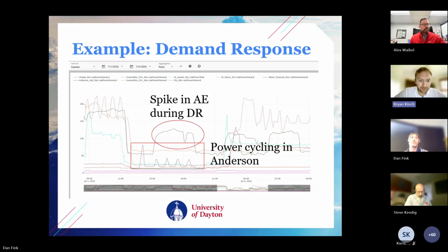So this example is during the demand response event. AE is Albert Emanuel, that's our admissions building. Somebody in Albert Emanuel called an HVAC tech and said, hey, turn our HVAC back on, it's too hot in here. So that spiked, almost 100 kW. They went outside the normal communication pattern, which is supposed to go through our office to prioritize what things get turned back on, so we're not negatively impacting ourselves.